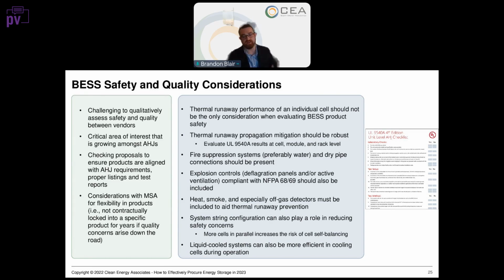We highly recommend due diligence early on, making sure our system is safe and listed to the expectations of that jurisdiction—contacting the local fire department or building department to confirm the system is listed. The procurement process involves the developer looking into the vendor to determine that the vendor has the latest safety reports, which they release to the developer, who then releases them to the AHJ.